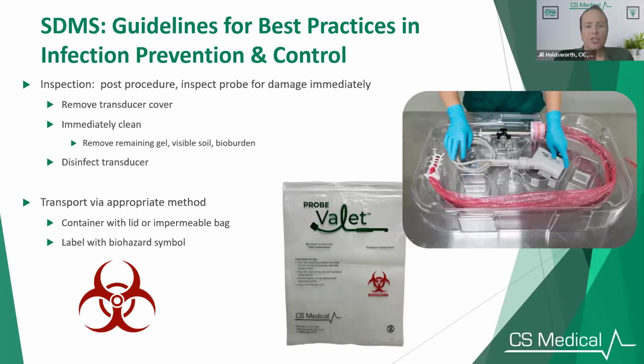So let's talk about inspection and transport. As soon as you do the procedure, we're going to be pre-cleaning, and all this time we need to be inspecting. Probes sometimes get ignored when we're talking about inspection because they seem pretty smooth on the surface. They don't seem like they need the inspection that a metal instrument needs to have, right? But that's wrong. We need to make sure that we are inspecting these probes for damage, for cracks, for small tears, micro tears, because anything that's compromising that probe, either on the shaft, on the cord, anywhere, can be a great place for bacteria to settle and biofilms to start to form. So trying to protect these probes from damage is of utmost importance.